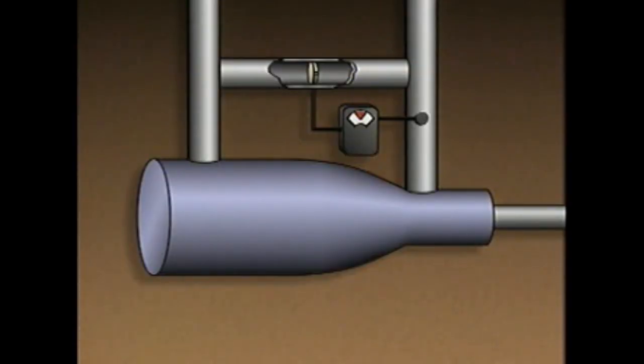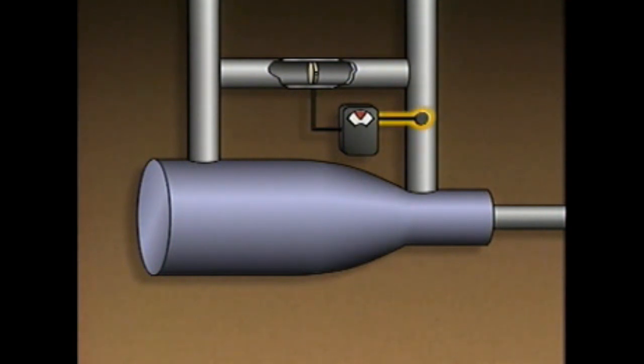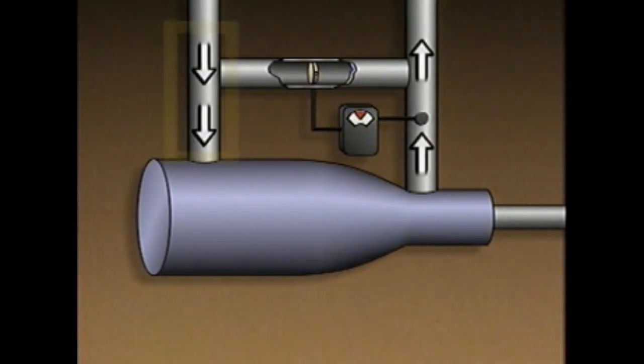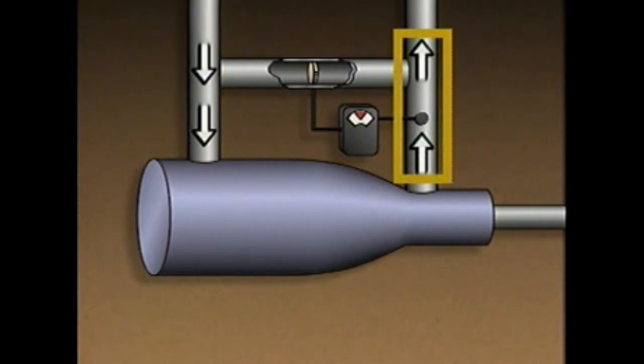This simplified illustration represents an axial compressor with a common type of surge control system. The control system consists of a flow sensor in the compressor's discharge piping, a flow controller, and a recirculation valve that's located in a section of piping between the suction piping and the discharge piping.